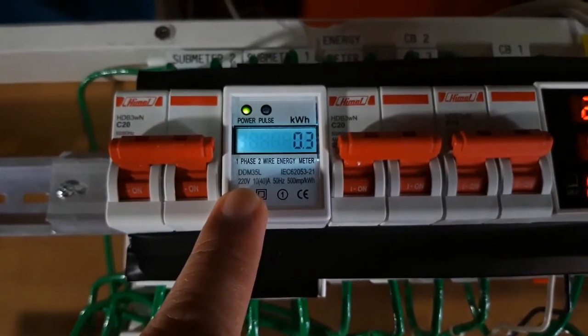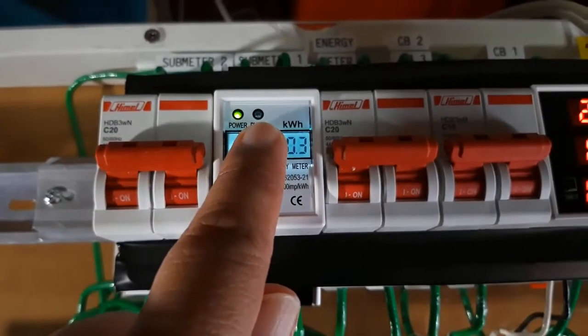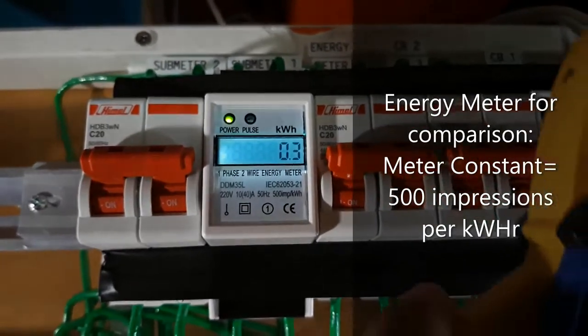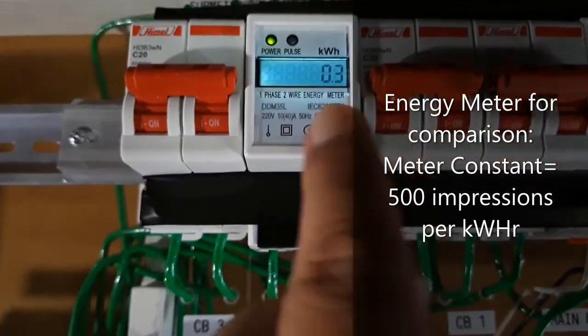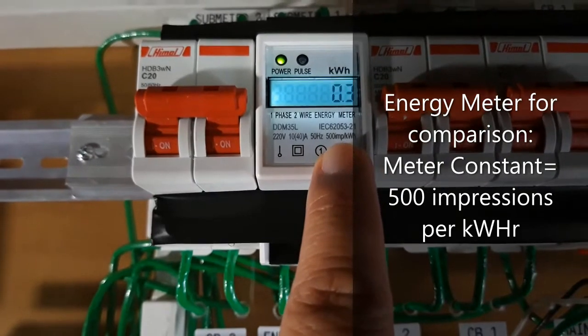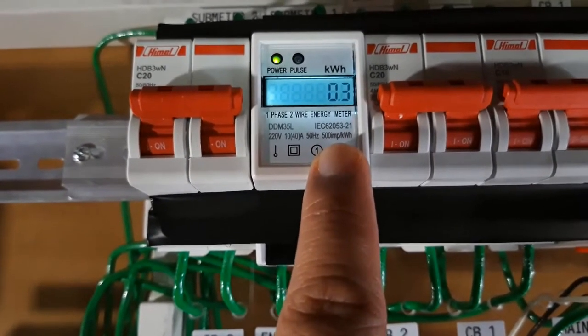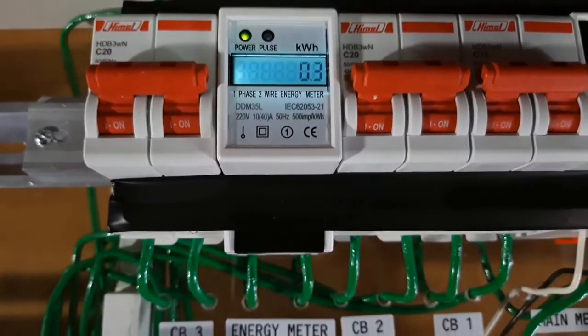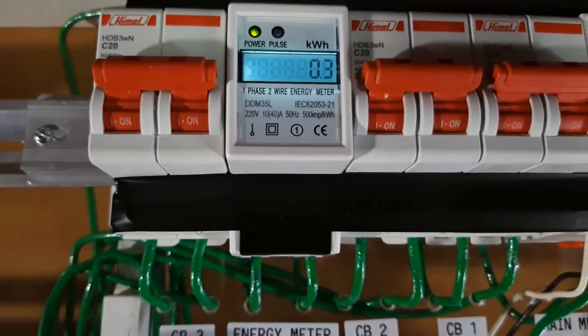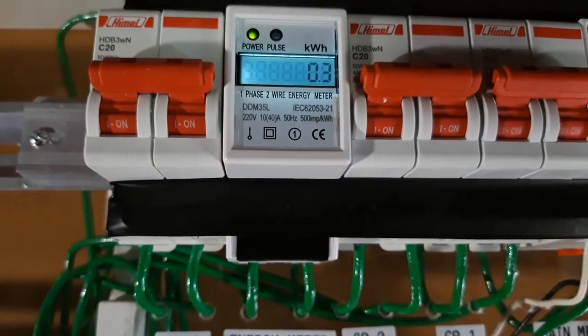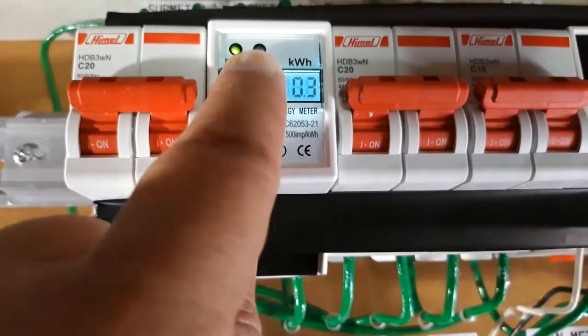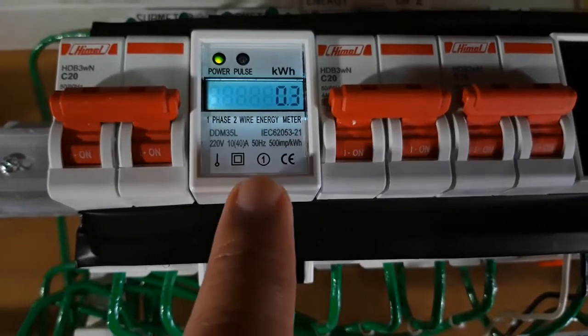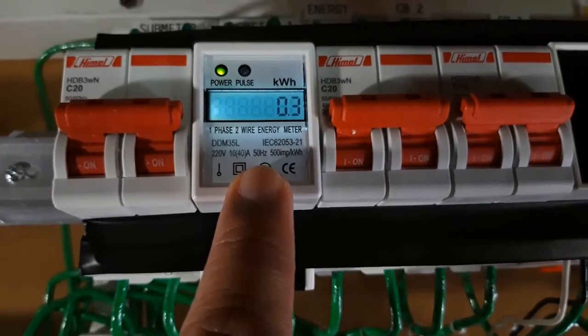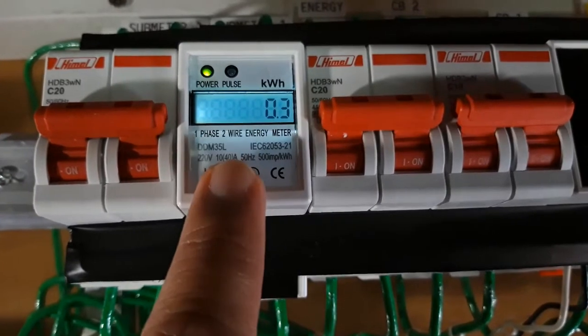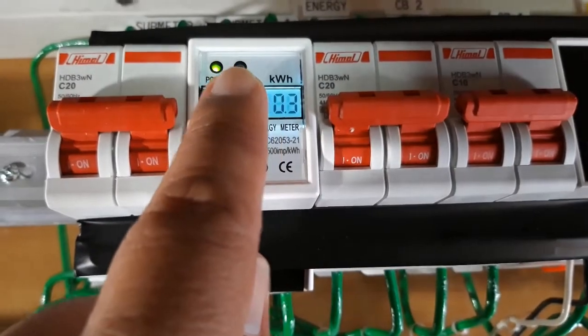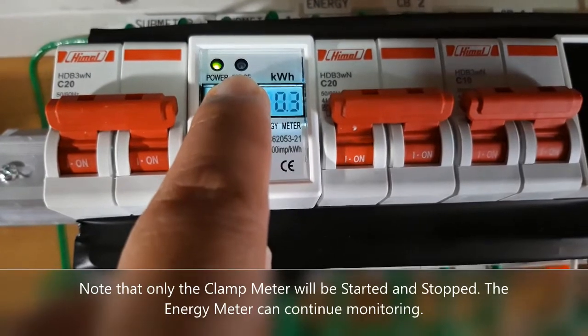This is the meter whose pulses we will synchronize with the Hioki clamp meter. As you can see, the meter constant here says 500 IMP per kilowatt hour. That means 500 impressions per 1 kilowatt hour, which is just another way of saying that the pulse here will light up every 2 watt-hour of energy passing through this meter.